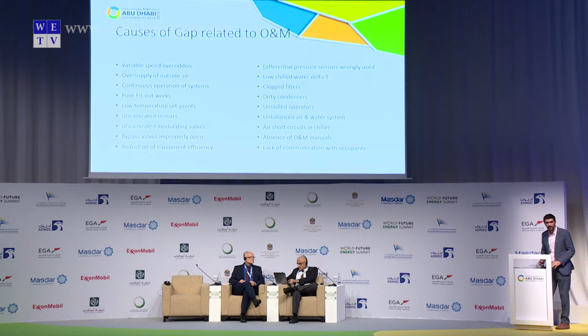Uncalibrated sensors. Many times in any building now, especially all the new buildings, you have lots of sensors to make them high performance. But if you don't calibrate these sensors on a periodic basis, these sensors will not give you the right information. Hence, the gap will increase. And so on and so forth. Probably I'm going to skip the rest now because we don't have too much time. But you may take note of those because they may be happening in your buildings.